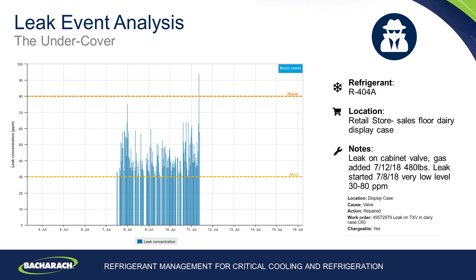Here is another example of refrigerant leak being detected on the sales floor. The leak detection coverage in this example was picking up key points across the sales floor to detect leaking refrigerant from display cases. Time was required by the engineer to triangulate where the leak was occurring and which individual display case was contributing. Due to the way that refrigerant disperses around the sales floor the PPM values detected were very low, but even though those PPM values were low, due to the volume and size of the sales floor the leak was large. The leak was identified in the display case, the valve was replaced, refrigerant was added, and the leak disappeared, reducing the amount of refrigerant that needed to be added.